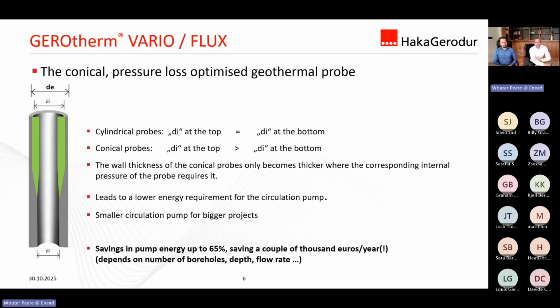So the conical probe Vario Flux, what is special about it? For a cylindrical probe, you have the inner diameter all the way through. So the inner diameter at the top of the probe is the same as on the bottom of the probe. With the conical probe, the upper diameter is bigger and the lower diameter at the U bend is smaller. So there you have a bigger wall thickness where you need the pressure resistance. Let's say if you're 300 meters in the ground, the ambient pressure is 30 bar, and there you cannot have a small wall thickness because otherwise if you grout it, then you squeeze the probe.